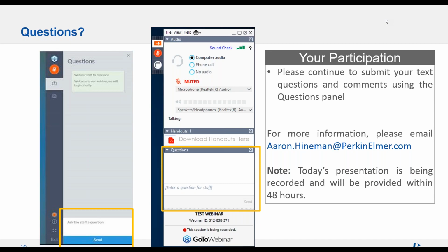Yeah, it's perfect. It kind of ties into the next question: can I run an analyte in both attenuated and non-attenuated modes in the same method? And yeah, basically, absolutely. Yep, that's what you do all the time during method development. If I have a high level, if I want to see which mode will be better for me, which will give me better answers, I'll run them both at the same time, or in the same method. So I'm only running the sample once, it'll measure both, and I'll have both answers for me.